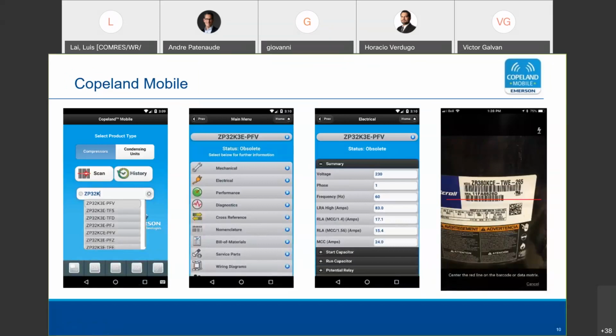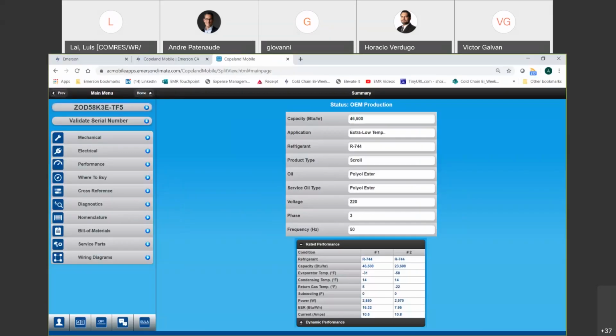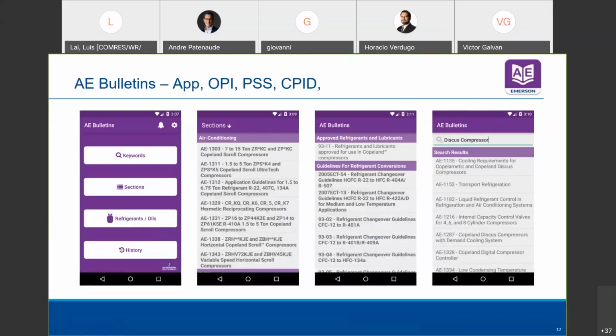Other software, Copeland Mobile, we've talked about this on biweeklies and so on. I'm not showing here a CO2 compressor, but they're in the software. Here's a CO2 compressor example. The newest ZOD58. It gives you basic capacities. If you click on performance, boom, you come down here. It'll give you its performance at a couple of rating points, minus 58 Fahrenheit, which is the very bottom of the envelope, and minus 31, and so on. So information is there in the tools.